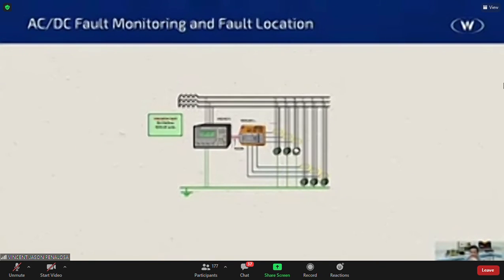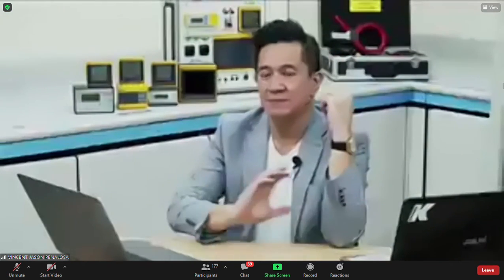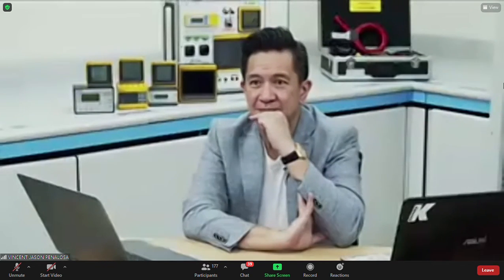All right, that yellow box that you see there on your screen, that device is capable of 12 circuits. Now, in one system, you can have as many as 90 of those devices. So it's 90 times 12, about 1,100. Sorry, I'm going to use a calculator. Sorry, 1,080 loads. It can handle 1,080 loads in one system. So you will have 90 of those yellow devices, and then you can monitor up to 1,080 loads.